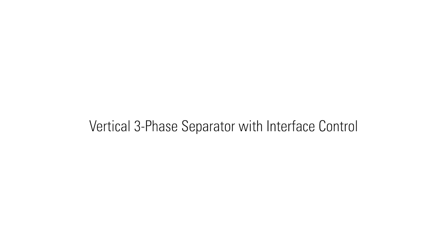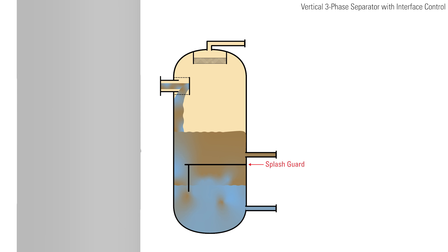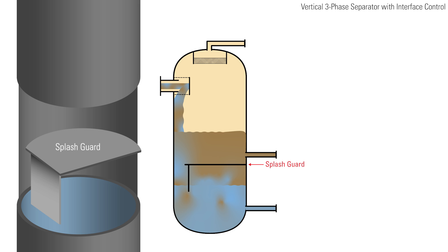In a vertical three-phase separator with interface control, the emulsion enters the vessel and immediately hits the inlet diverter plate, separating the bulk of the gas upon entry. The inlet diverter also directs the emulsion down along the sidewall, minimizing disturbances to the fluid. Lower in the vessel, the emulsion encounters a splash guard to further minimize agitation. This baffle is open and allows the emulsion to flow downward while protecting direct interaction with the interface level controller to prevent a false reading of the fluid level.